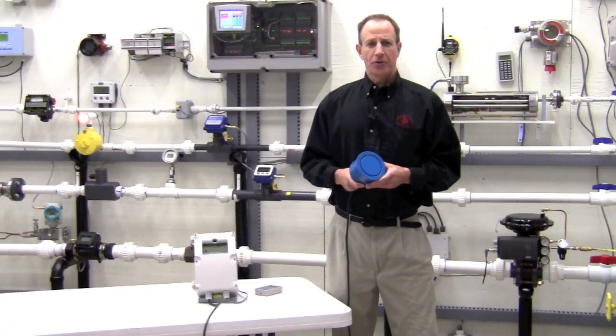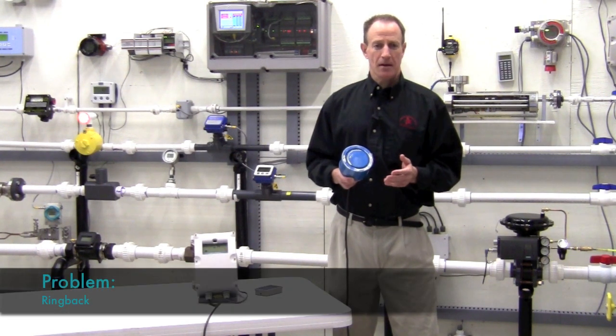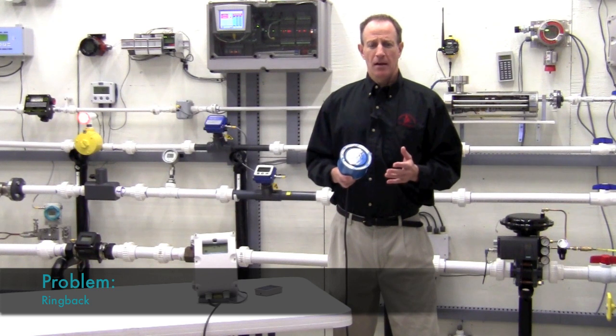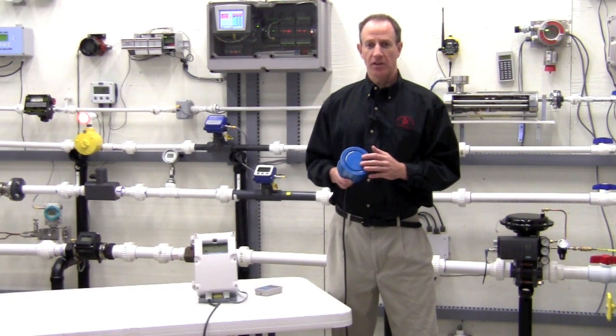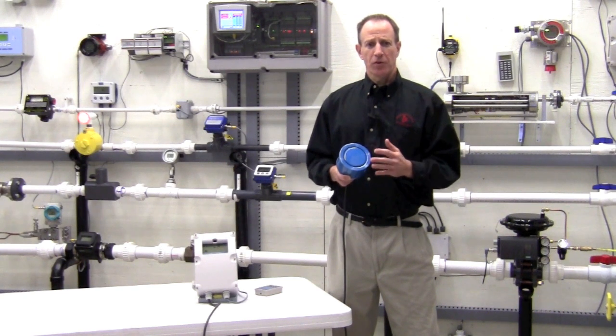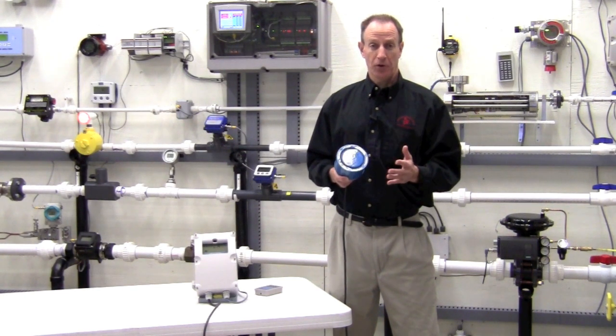If the Hydroranger occasionally displays a level higher than the actual level, the sensor may be experiencing ringback. With ringback, the transducer face continues to vibrate after the transmit pulse has ceased. What this means is the sensor was still ringing when it's time for the sensor to start listening to the return echo.